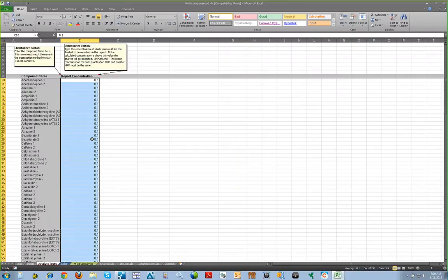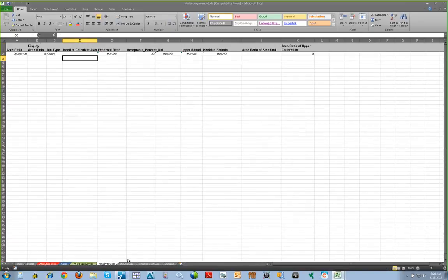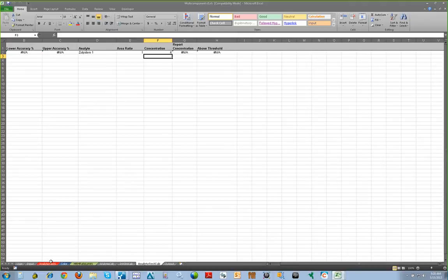Query files can be customized to flag results based on any data parameter you like. In this case, the query file will flag results based on analyte concentration, but this column can be customized to flag based on peak areas or other data criteria. The other tabs in this Excel sheet are performing the calculations and do not require modification. Our AB Sciex application support team can provide you with query files and help you to modify query files as needed to support your data processing needs.